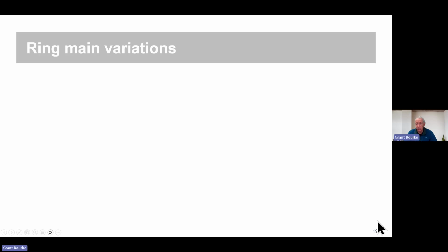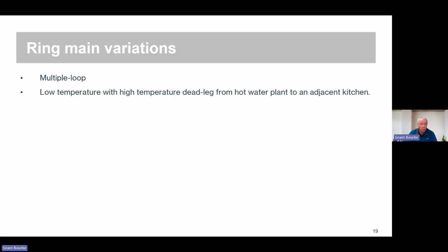Within those two main systems, and we're not going to cover them tonight, you can dream up many different combinations of those systems and many different things that you might do with them. We can have multiple loop ring main systems. If your hot water plant's in the middle of the house and you've got wings going either side, you can run a loop to either side. Obviously, large buildings in particular have multiple loop ring main systems. We can have a low temperature ring main, but if we can get our hot water plant close to the kitchen, we can maybe take a dead leg just straight from the hot water plant to the kitchen.